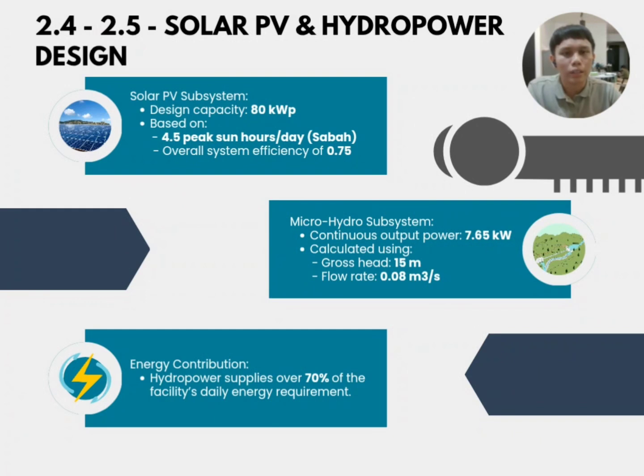The micro hydro subsystem, on the other hand, provides a continuous output power of 7.65 kilowatts. This is calculated using the gross head of 15 meters and also the flow rate of 0.08 cubic meters per second. And for the energy contribution, the hydropower supplies over 70% of the facility's daily energy requirement, improving overall reliability.